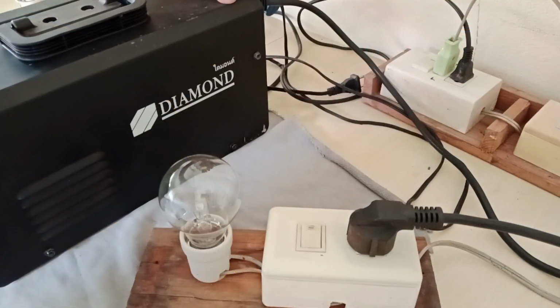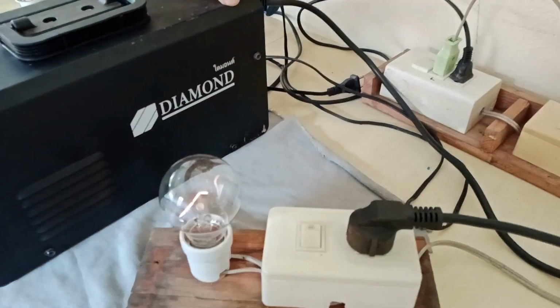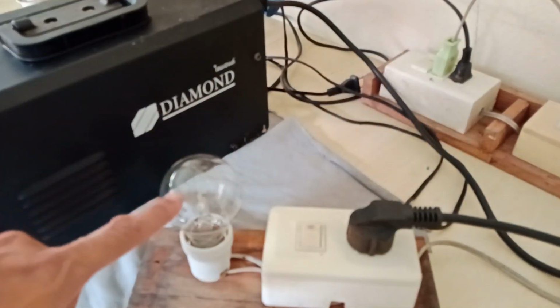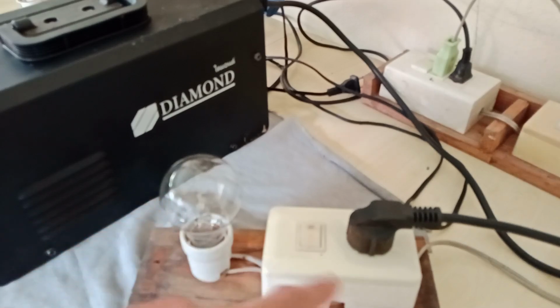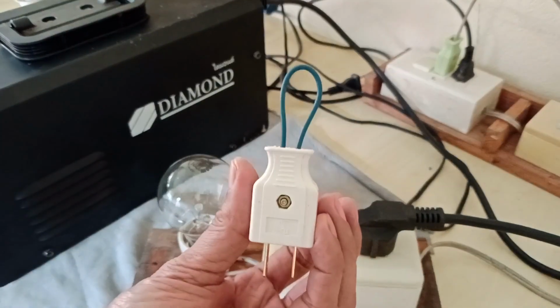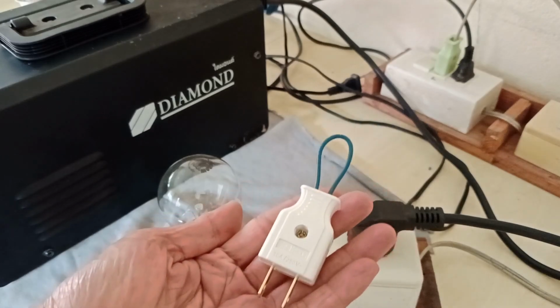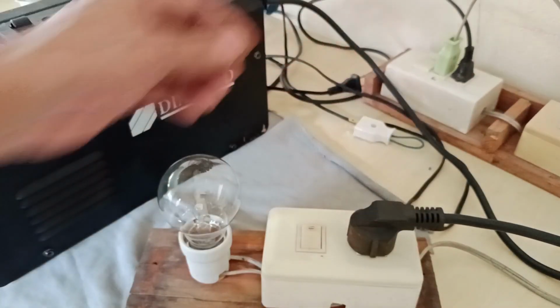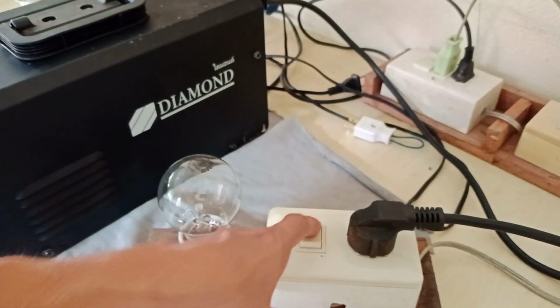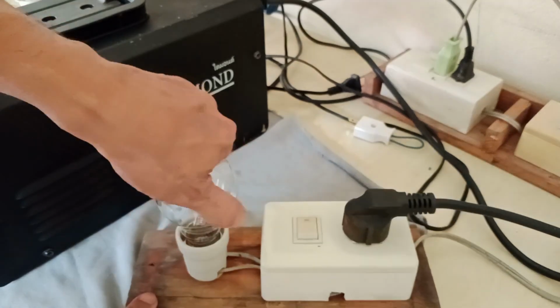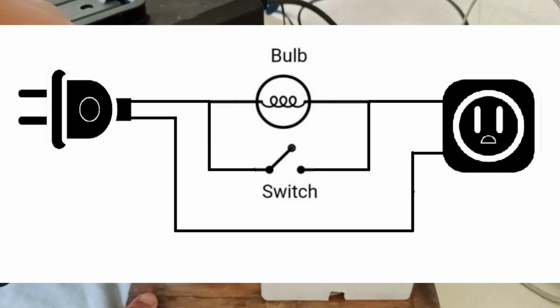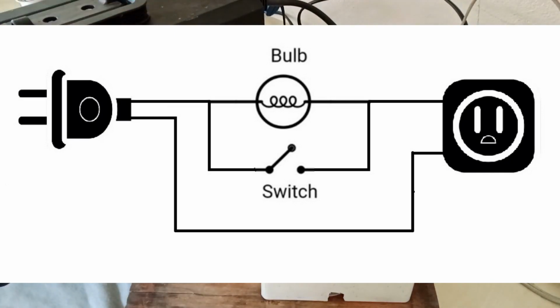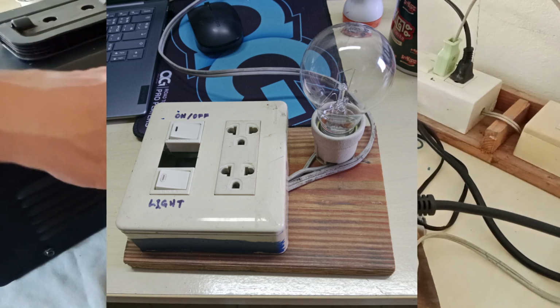Now I will show you the fixture I used when working with inverter welding machine repairs. This is a 100 watt 220 volts light bulb connected in series to the AC line. So for example, you have a short circuit connected to this outlet, like this plug right here, that I use for testing. The bulb will just light up brightly, but it will not trip the house circuit breaker. The switch right here will bypass the light bulb in order to deliver normal power to the device that is plugged in, only once it is confirmed that there is no short circuit. Here is the circuit diagram of the fixture, together with a photo of the other one that I have.